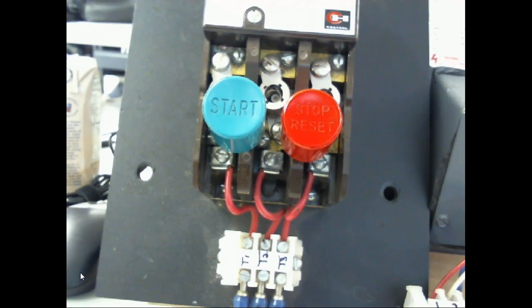And this has happened before, you know. One of these warehouses down here, one of our guys worked on it, and they had one of the motors that wouldn't start. It kept kicking overloads and stuff like that. And guess what they did? They changed the variable speed drive out of that thing. You know how much variable speed drives cost? A lot. Guess what was wrong? One of the motor connections came loose.